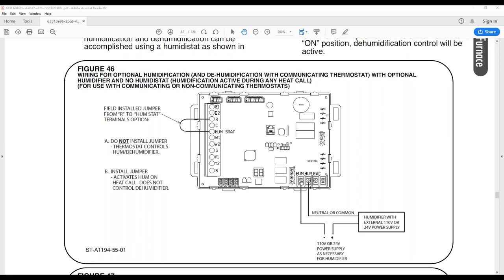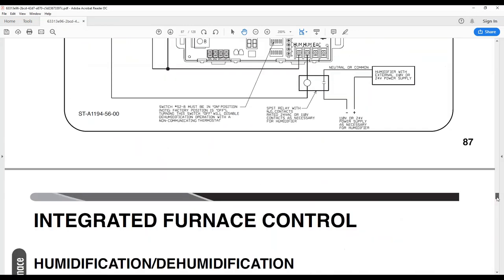So here are the contacts down. Let me get a different pointer. The contacts down here are your dry contacts. So it closes the relay and then closes the contacts, sending power down to your humidifier. Notice you are supplying power from a separate transformer. If you have any questions at all while we go through this humidification, let me know.